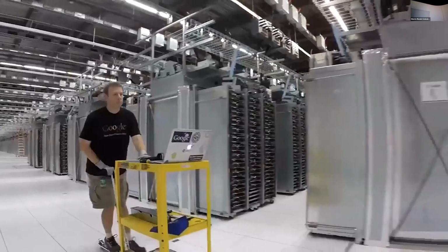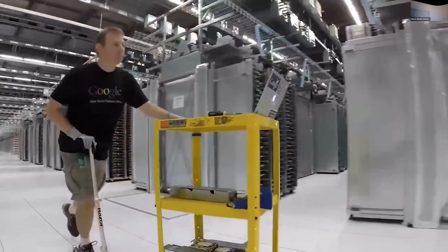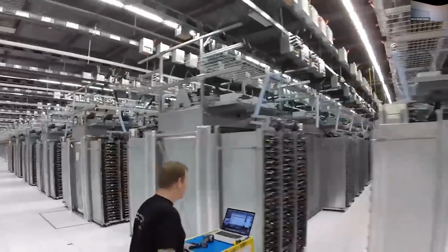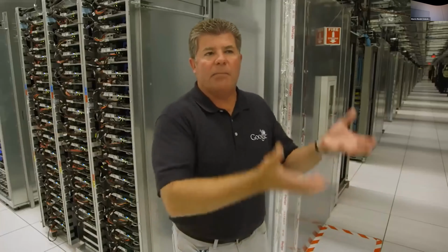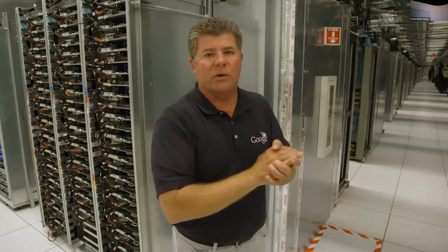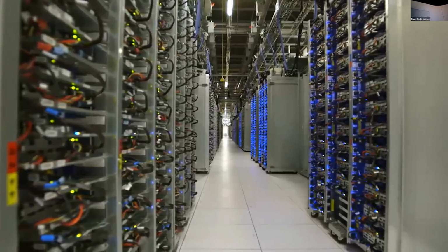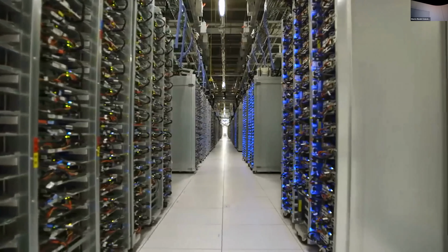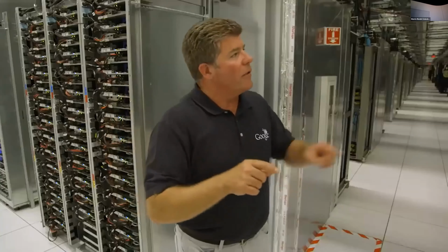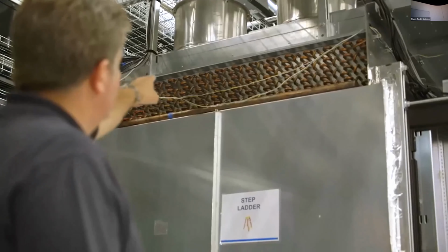In the time that I've been at Google for almost 6.5 years now, we have changed our cooling technologies at least 5 times. Most data centers have air conditioning units along the perimeter walls that force cold air under the floor that then raises up in front of the servers and cools the servers. In our solution, we take the server racks and we butt it right up against our air conditioning unit. We just use cool water flowing through those copper coils that you see there.